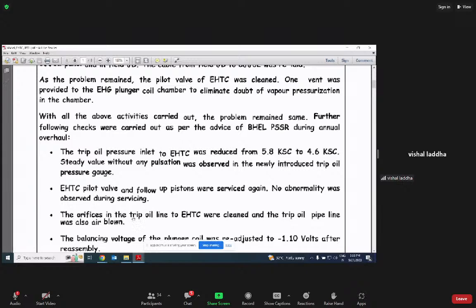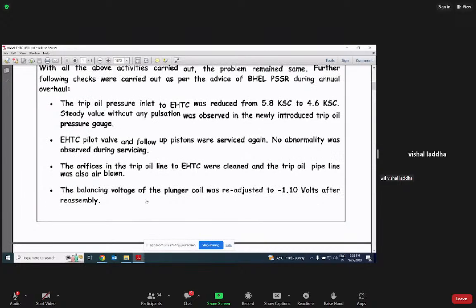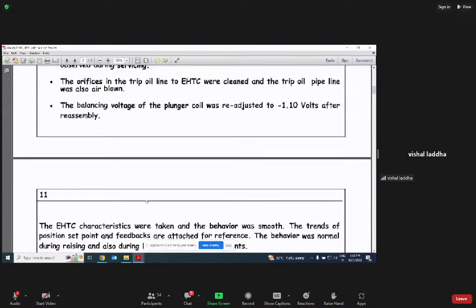The orifices in the trip oil line to EHTC were cleaned and the trip oil pipeline was also air blown. The orifices are just below the auxiliary follow-up piston. All the orifices were checked and cleaned, but still the problem was the same. Even the plunger coil balancing voltage was in a doubtful position, so the balancing voltage of the plunger coil was readjusted to minus 1.10 volt after reassembly of all the systems.